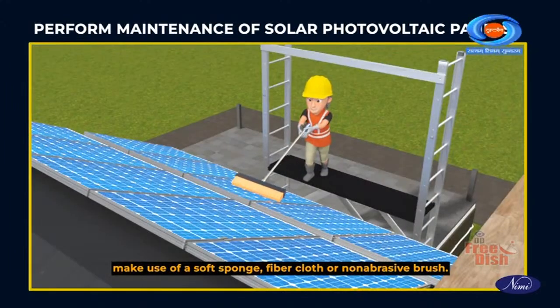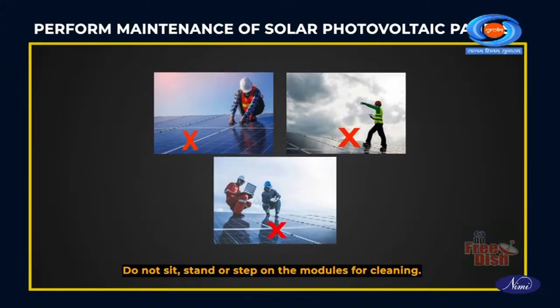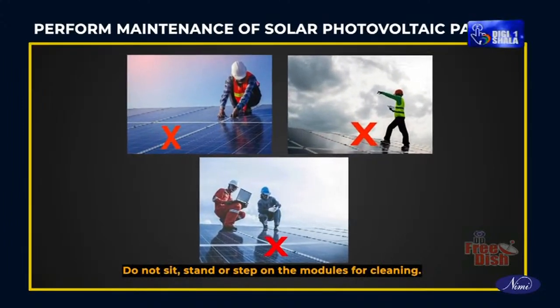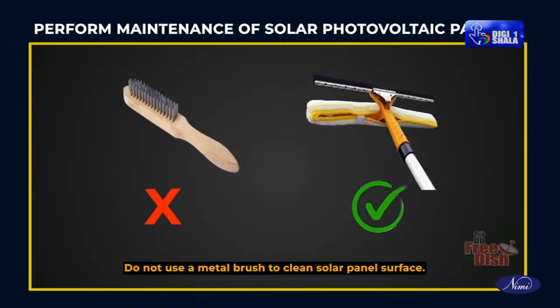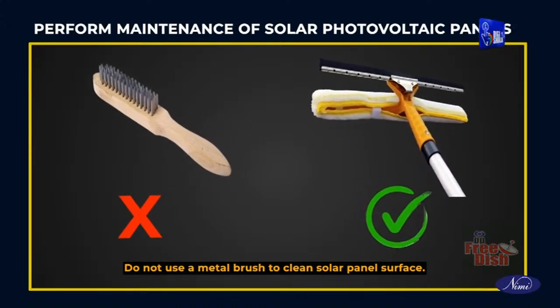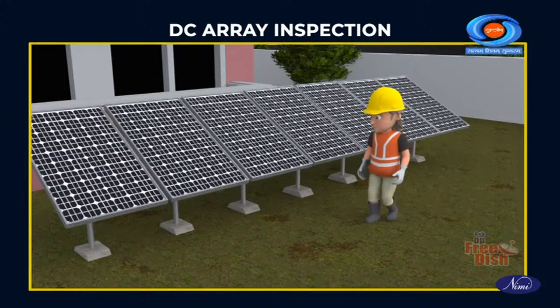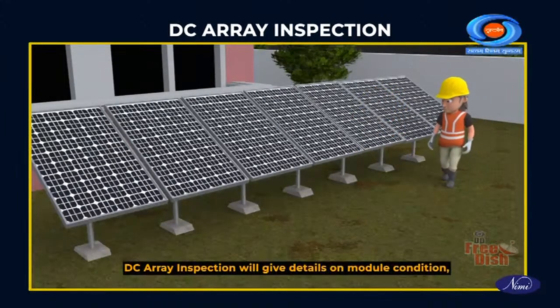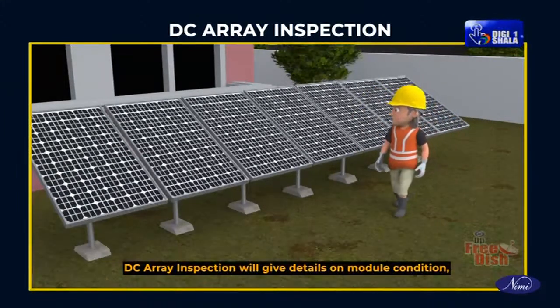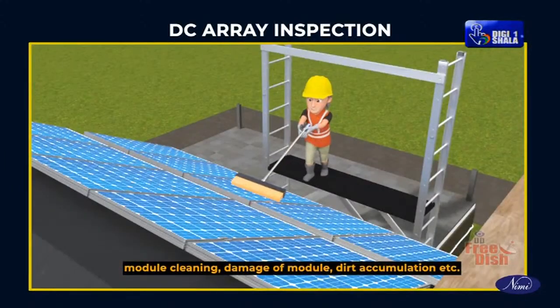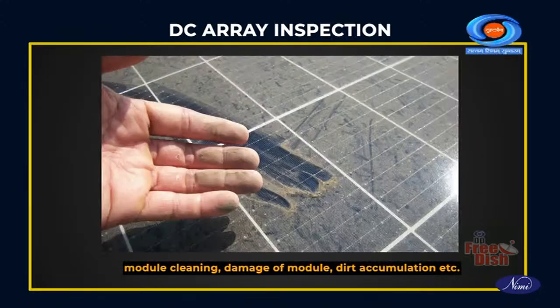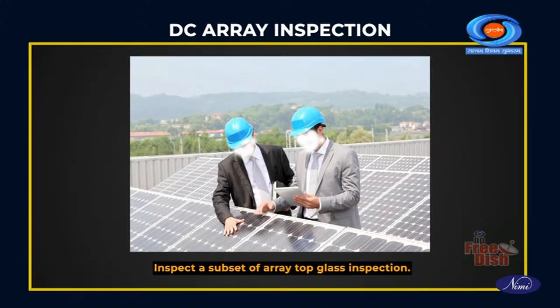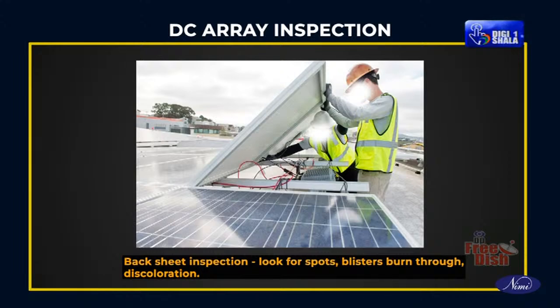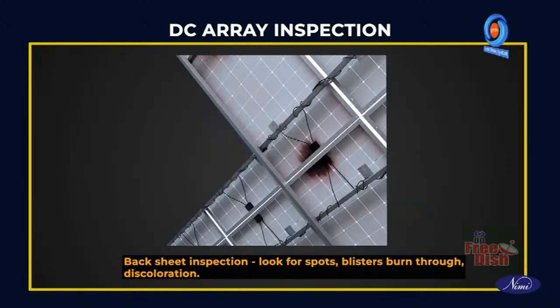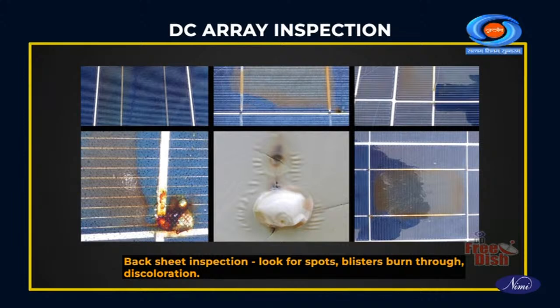or non-abrasive brush. Do not sit, stand or step on the modules for cleaning. Do not use a metal brush to clean the solar panel surface. DC array inspection. DC array inspection will give details on module condition, module cleaning, damage of module, dirt accumulation, etc. Inspect a subset of the array, top glass inspection. Backsheet inspection. Look for spots, blisters, burned through, discoloration.